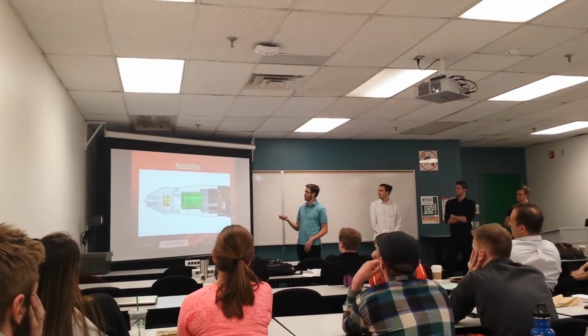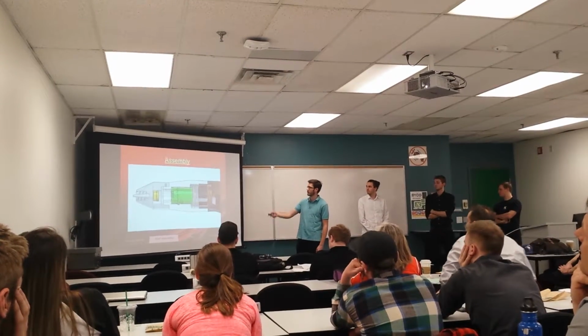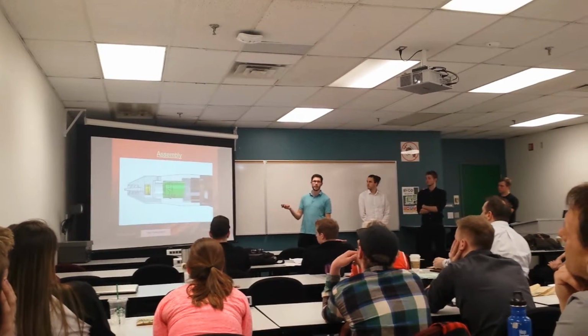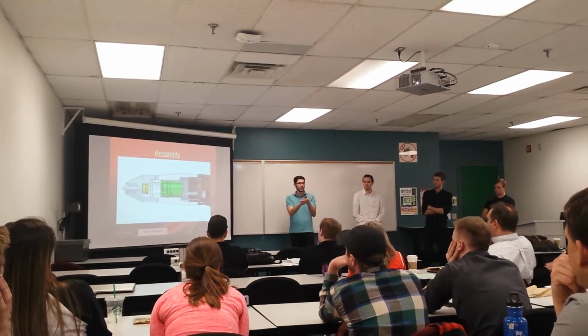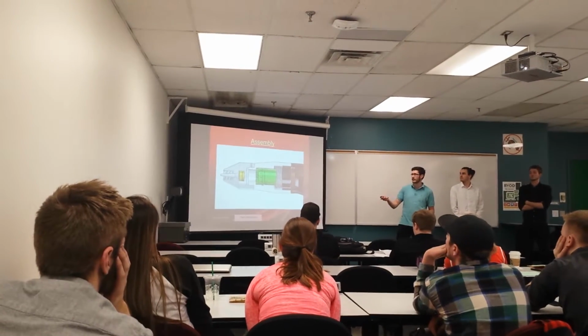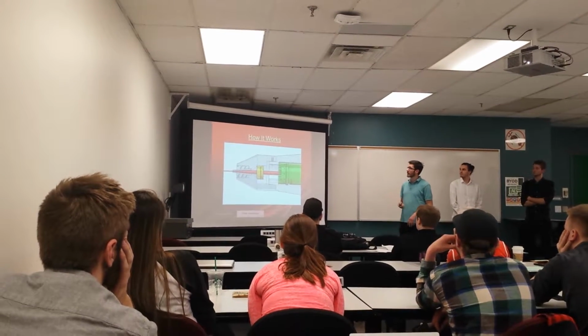This would be the collimating tube, which would be inserted in there, making sure that there's no leeway for it to move around at all, and it's fastened by this ring. The distance between the actual aspheric lens and the collimating tube wasn't too big of an issue because the beam coming out of the collimating tube was collimated, so it didn't diverge too much based on the distance. But the distance between the exit point and where the tip of the funnel ends was the really crucial part, because if that's either too short or too long, you're getting a completely different diameter. And this is how it works.